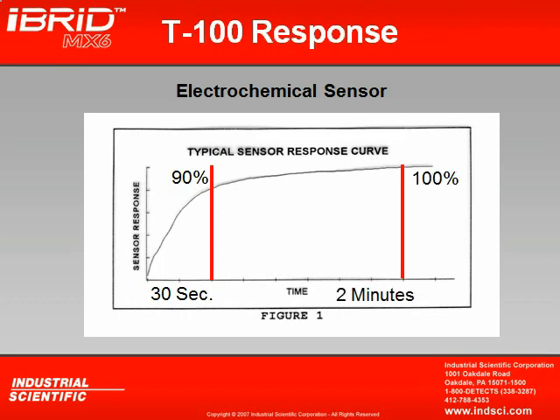For example, let's say you go into an environment that has 200 ppm of carbon monoxide. Your instrument should be reading approximately 180 ppm within the first 30 seconds. Now to get the full 200 ppm response may take as long as 2 minutes.